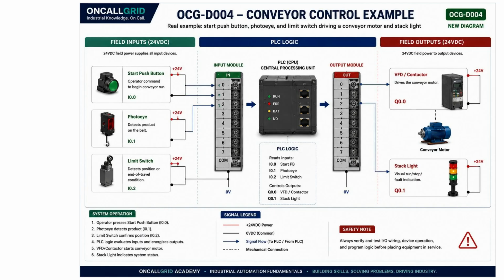Let's put it together with a real example: a conveyor system. A start push button, photo eye, and limit switch send signals to the PLC inputs. The PLC continuously evaluates those inputs using its control logic. When the required conditions are satisfied, it energizes the output, controlling the VFD/contactor, which starts the conveyor motor. At the same time, it drives the stack light to indicate the machine's operating status.